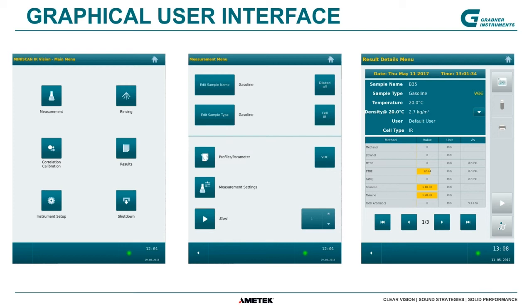The graphical user interface of the IR Vision is a little different from the vapor pressure and flashpoint instruments, but it is still very intuitive. You have the main screen; when you want to do a measurement, you click on Measurement, where you can set different parameters, but basically you press Start and provide the sample. Afterwards, you get the results. The results page has a header section with typical sample features such as density and other parameters, then a list of results. The yellow bars overlaying some results indicate the typical expected range, giving a good indication if you are outside or within range — and this range can be flexibly configured.